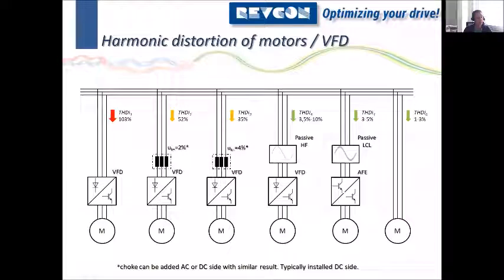Okay, so next one is 35% THD on a drive with a 4% choke. That's quite typical on the market. 4% is more or less the benchmark from any quality supplier on the market right now. To get further down, you can't just add up the impedance inside the drive or the inductance inside the drive. You will have to place some kind of harmonic solution to your situation. So a passive harmonic filter would cause you a THDI of 3.5 to 10%, depending on brand, depending on the performance level you choose. I think barely all suppliers offer you different performance levels of their harmonic filter.